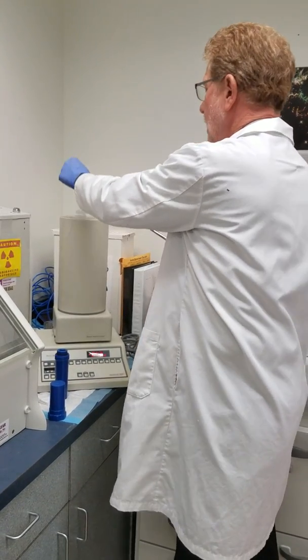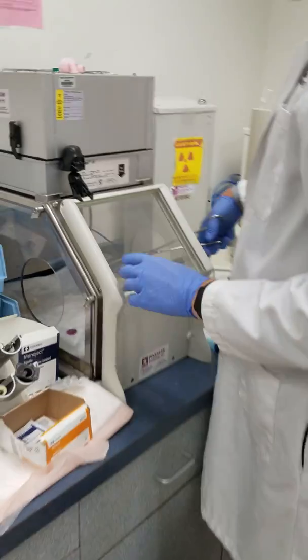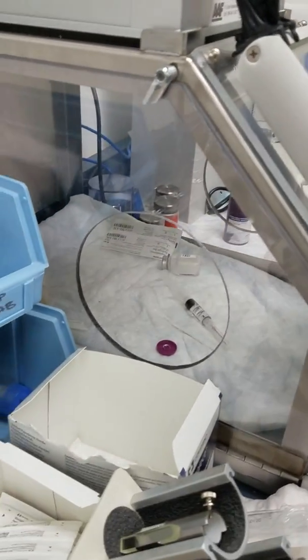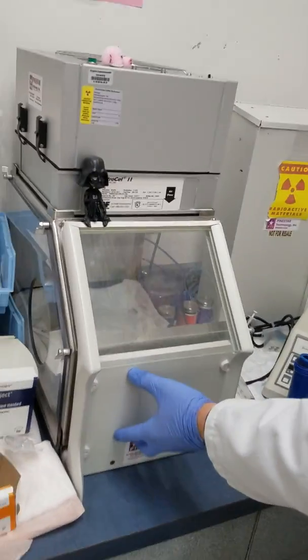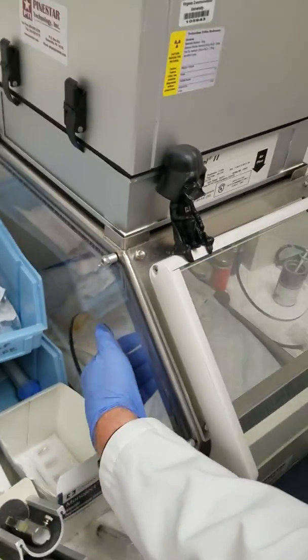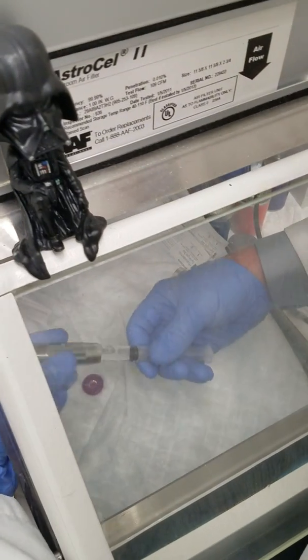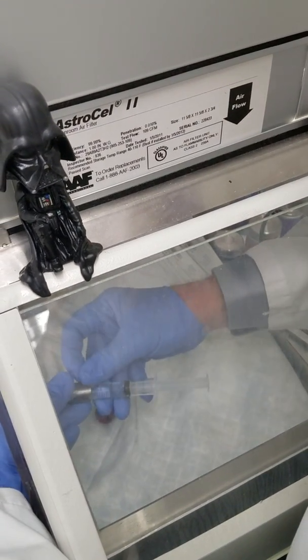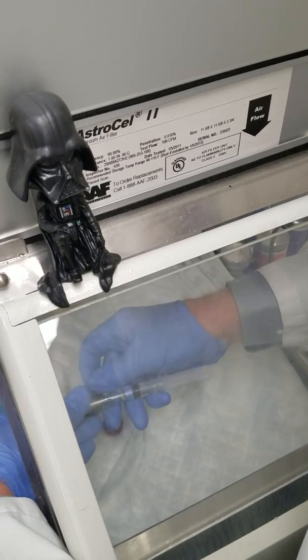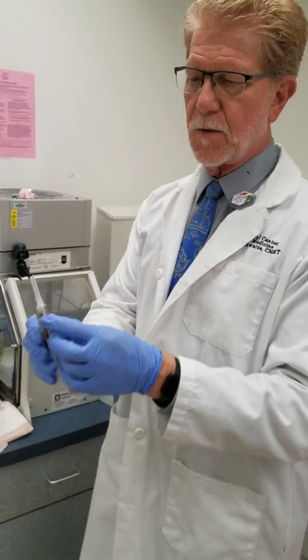Now we pull out the syringe and place it in here. This is a small L-block — the lead glass and lead shielding protect us from the radiation and allow us to work with the radioactive isotope. I take a syringe shield, place it into the container, open up the screw a little, then tighten it down. Notice there's also a lead glass window here, because when you inject the patient's vein, you want to see blood pull back into the syringe.